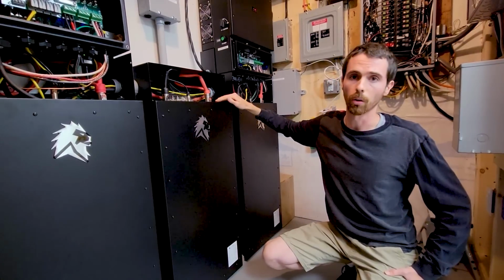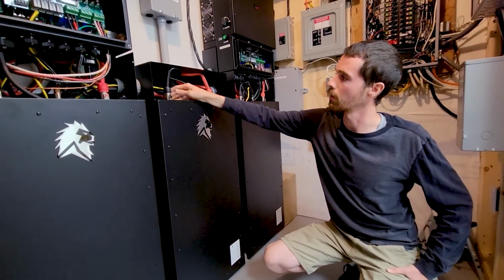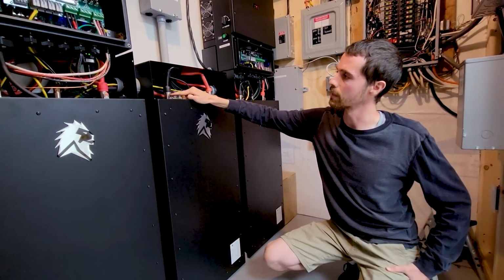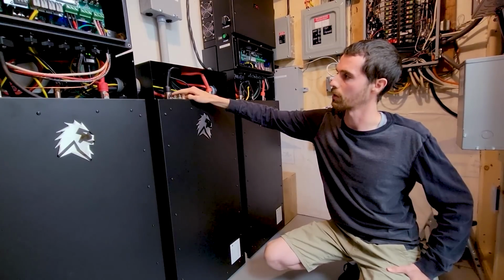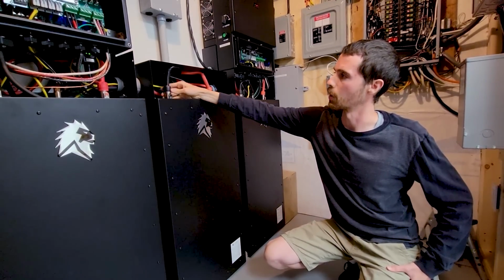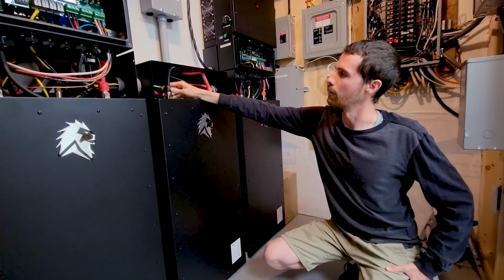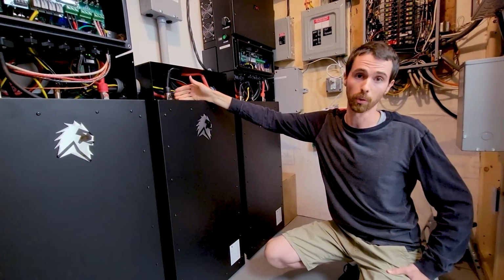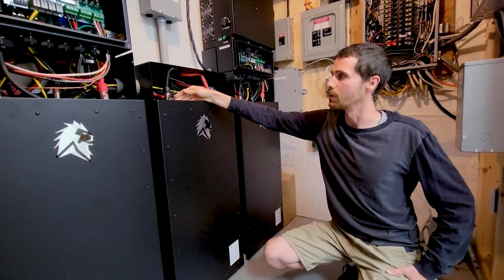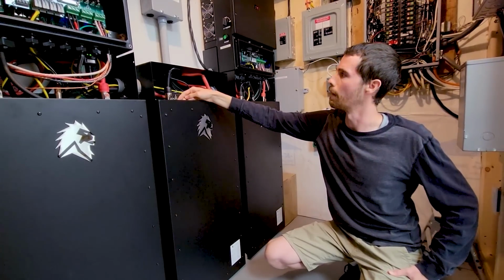What I like about this LionEnergy system is they use a nice connector. This is metal, but is insulated on the outside from the connection, from the connector. So this is not live. Otherwise it would short out. But these are really nice connectors, very sturdy, and they're much better, for an installer, than using nuts and bolts to make the connection.